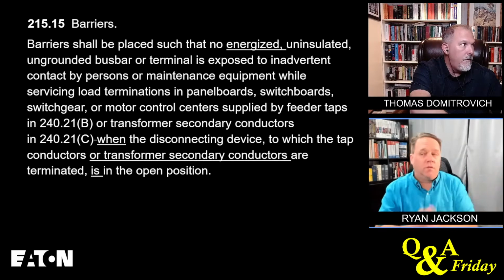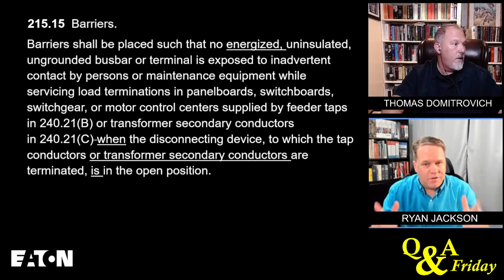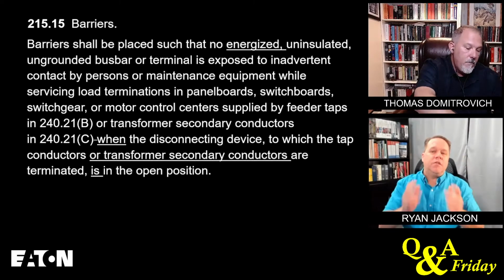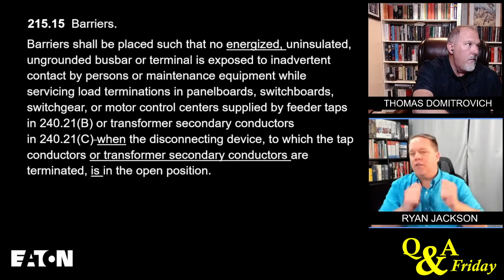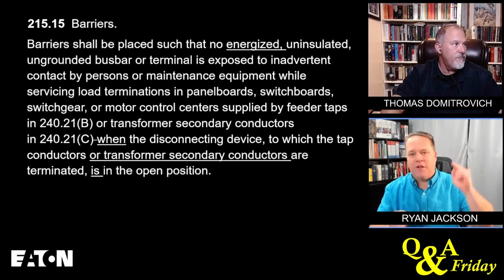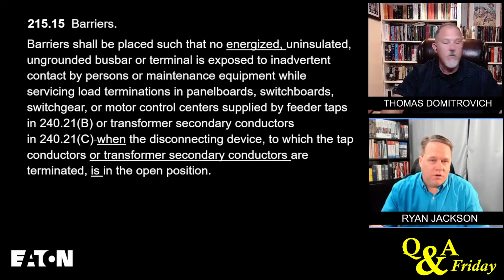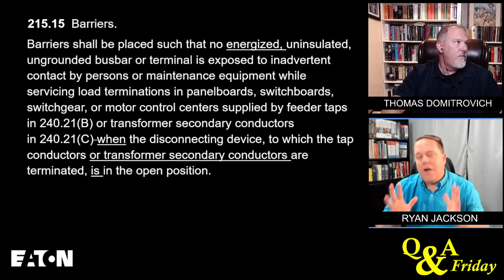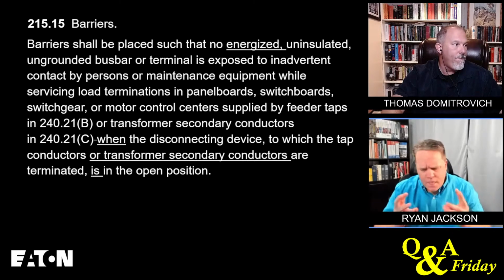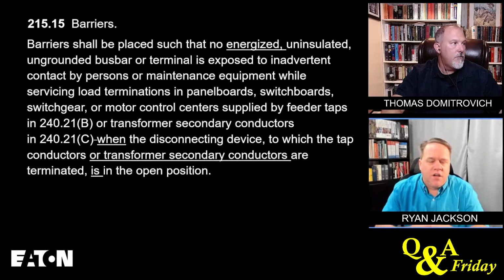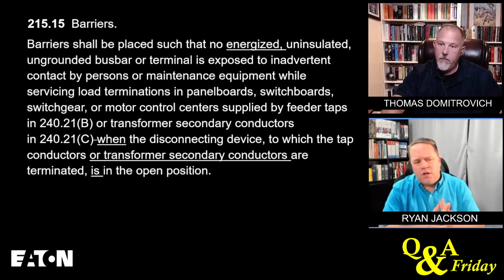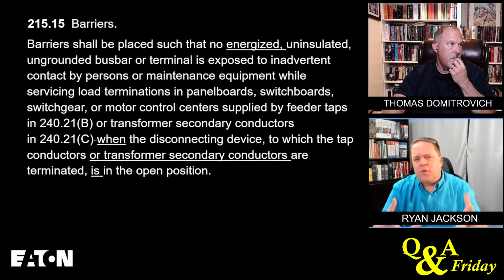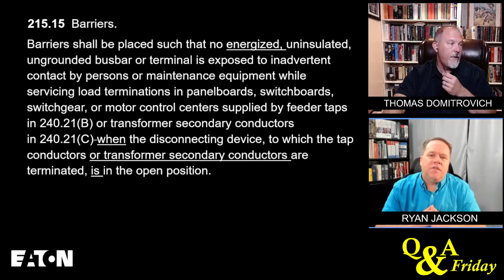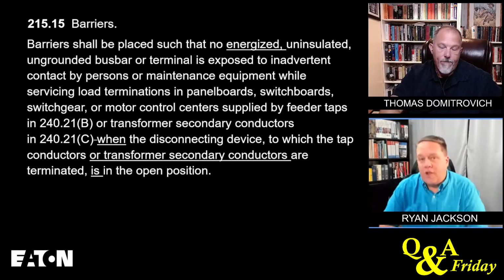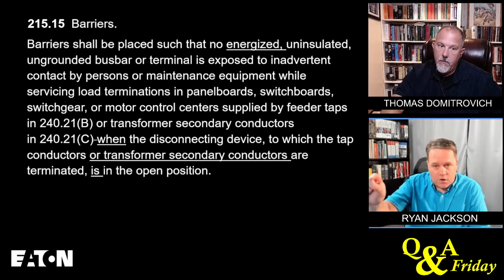And look, we live in the real world. How often is that going to happen? Not that often. Right. We beat electricians over the head with OSHA and 70E, and we yell and say, work safely and turn it off, and then don't give them a realistic way to do it. That barrier gives you a realistic way of working in a de-energized condition, in an electrically safe work condition. Now, what you have here in your language is if it just says transformers that are supplied from tap conductors, I think that, number one, that's going to give you 99% of your transformers. It's going to give you those barriers, which is what you want.